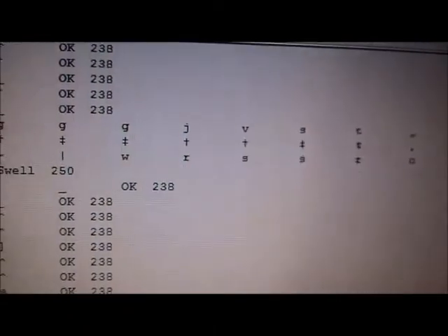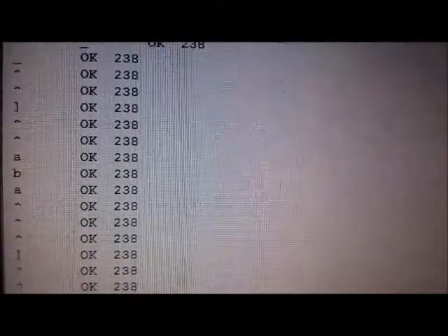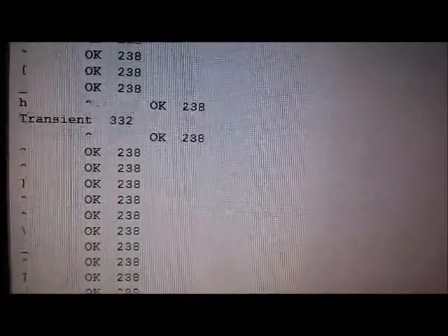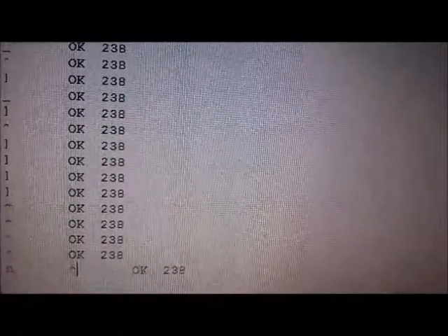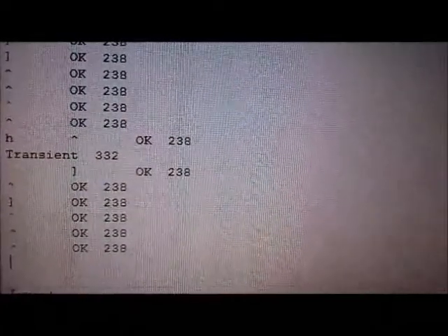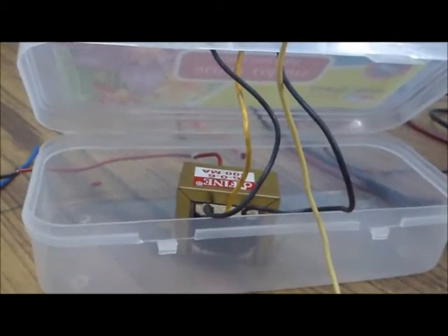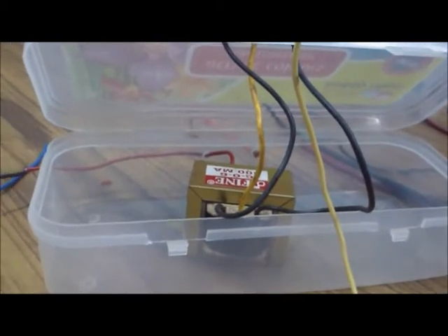Similarly, as we increase the voltage, if the voltage is greater than the swell threshold for multiple cycles, then it is displayed as swell along with the voltage value. If there is a change in the voltage for a small interval of time, it is displayed as a transient. Similarly, for low voltages, sags are detected below the sag threshold value, and low voltage transients are also measured.